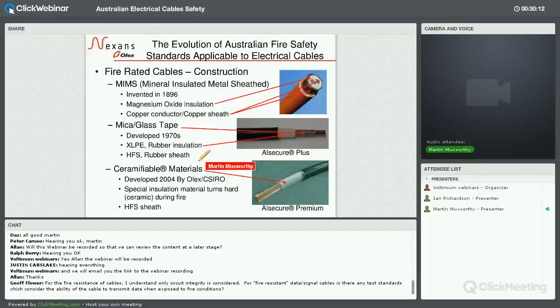Not until a new group of materials came along, which are called ceramifiable, and they were developed around 2004 jointly between OLEX and the CSIRO. Very special proprietary insulation material, and it basically turns to a hard ceramic-like material during a fire. So it's quite an ingenious and special material, and as you can see, as opposed to the mica tape cable, this particular cable only has 2 layers.